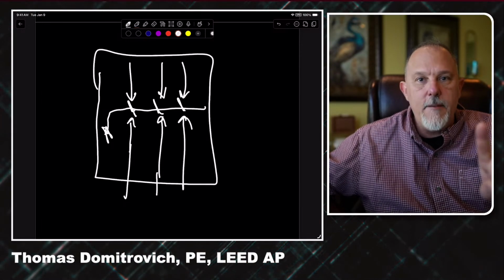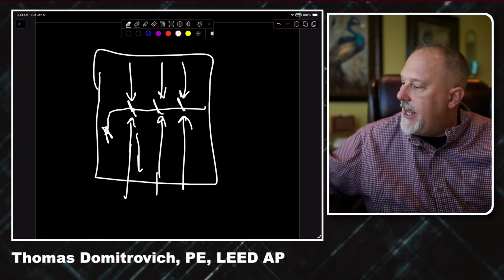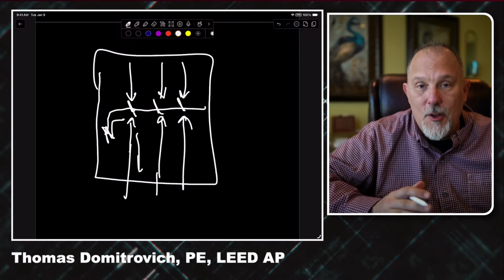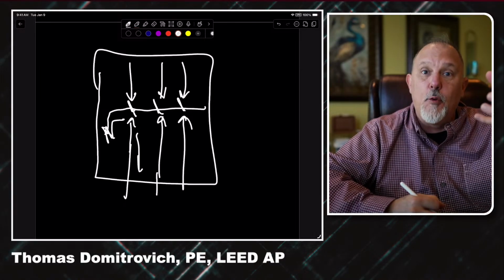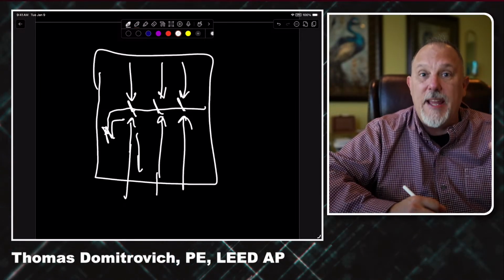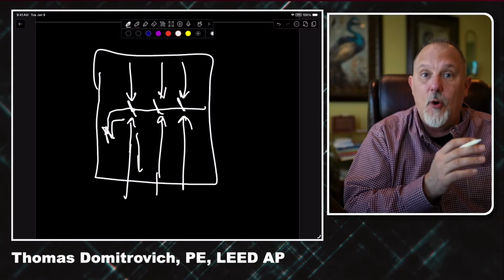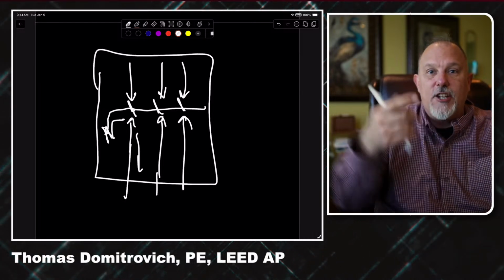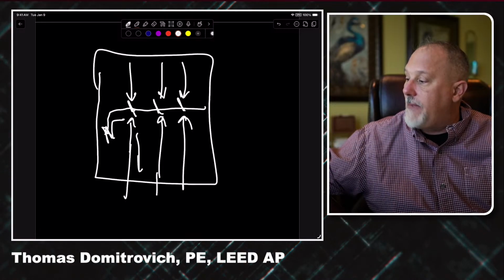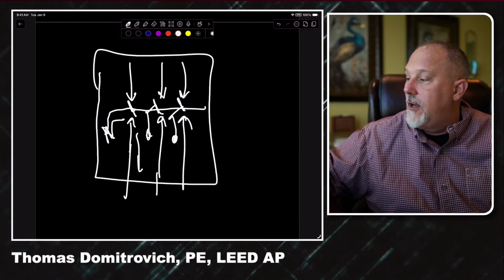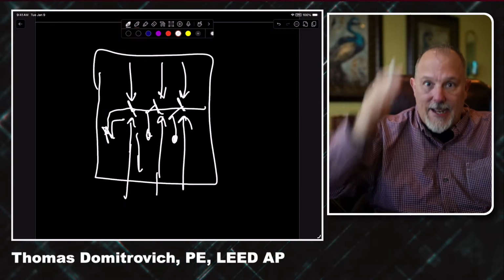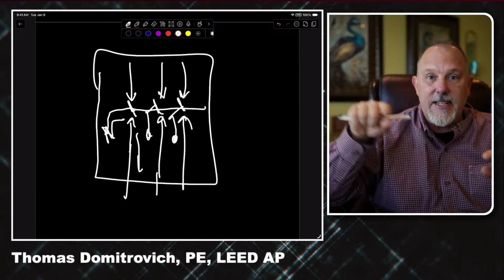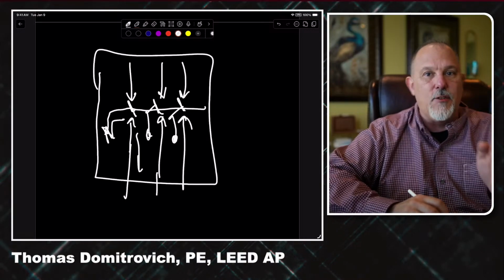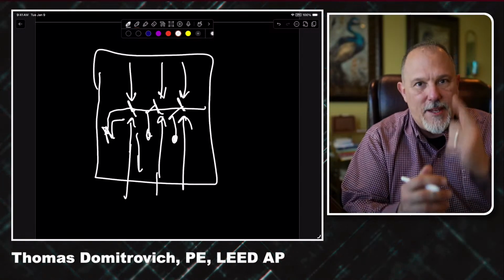In some cases, it's one mechanism that operates off of the fault current. And if I only have one pole that is pulling and seeing the current, then the force on that mechanism is going to be lighter, which may mean it takes longer to open, okay? Or I might need a little bit more current if it's one pole trying to open all 3 poles. In many cases, there's a mechanism for each pole so that I don't see a response in the time current characteristic curve. And the TCC curve that you see plotted is the same whether it's a single phase, 2 phases, or 3 phases. So be careful, take a look at the time current characteristic curves for any differences there. All right.